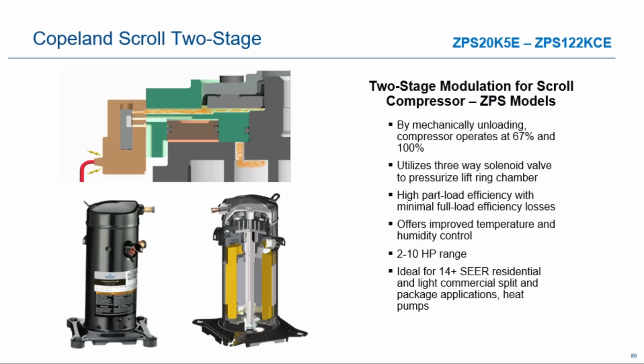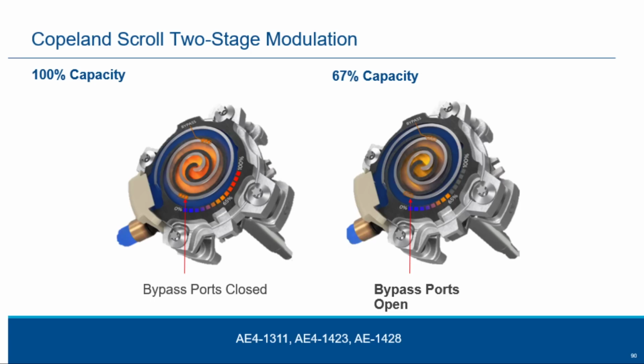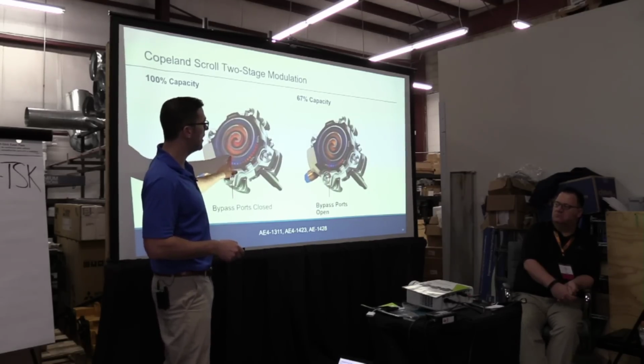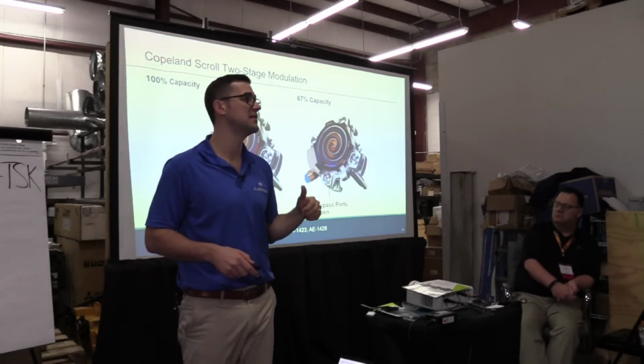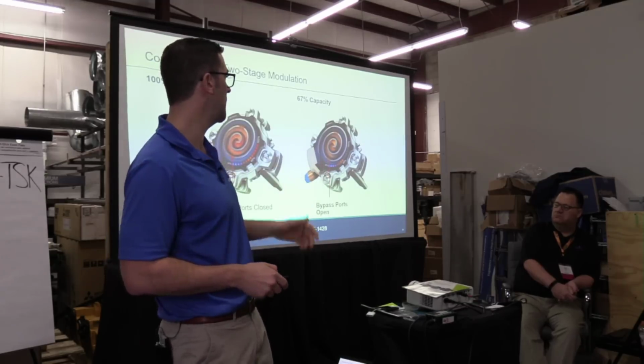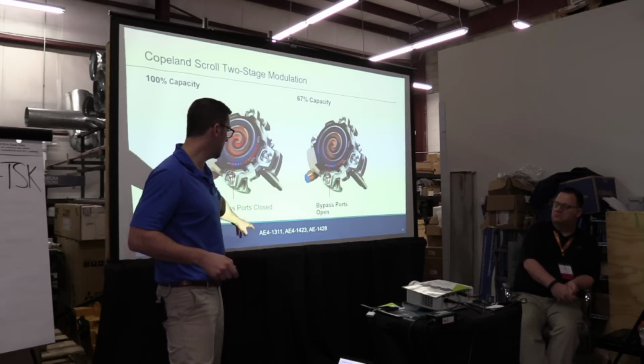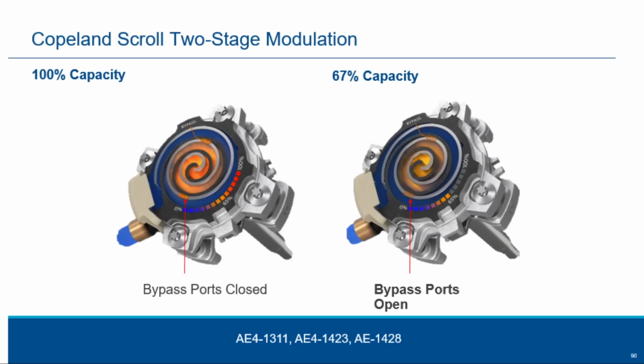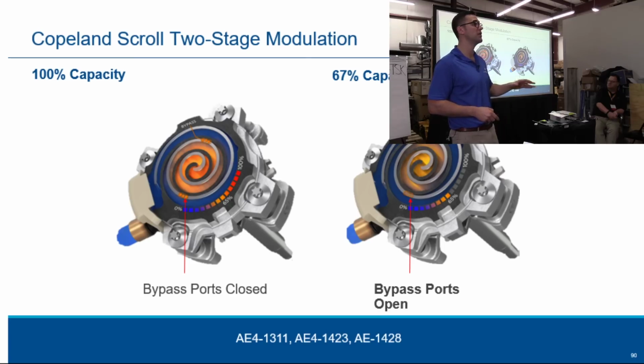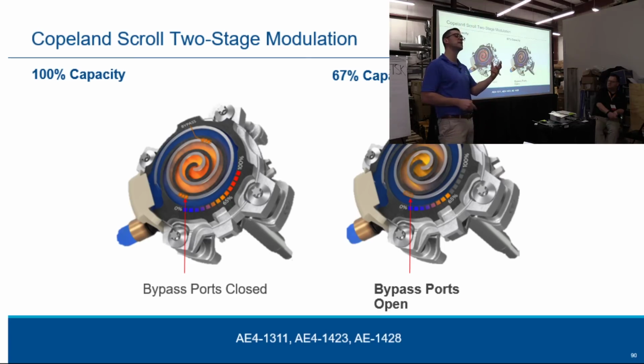What kind of advantage could this be in a residential home? What's the advantage of having multiple stages? High load, low load. What else? Better efficiency, humidity, right? Lots of good advantages. So here, this is how it works. You've got bypass ports. They'll open and close. It's 100% when they're closed. When they're open, it bypasses, 65 or 67%. It's all done on a solenoid inside the compressor. Down here, I've got AE bulletins. See, there are three different ones that talk about it. So sometimes there are multiple AE bulletins talking about compressors. It's very important to find those and understand them so you know how that compressor operates.